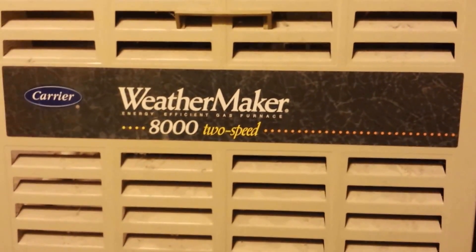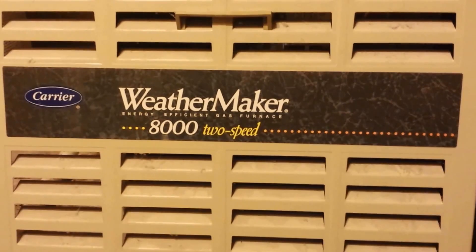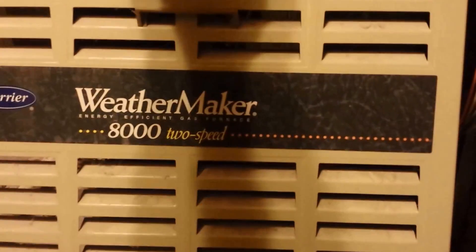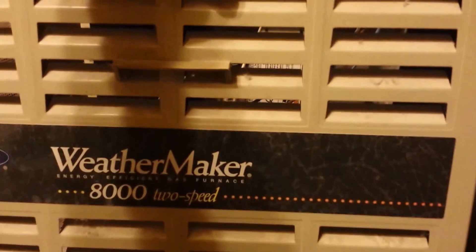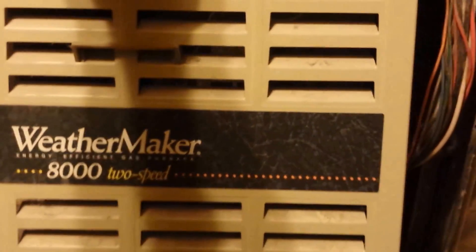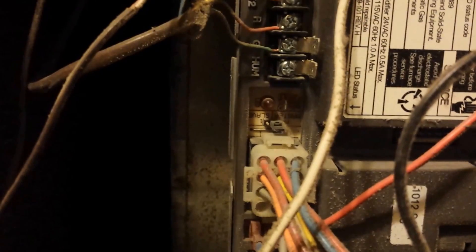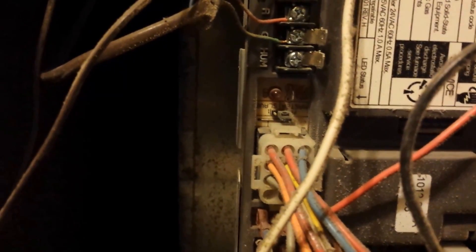I have a WeatherMaker 8000 carrier furnace that was giving error code number 33. The way you can tell is the little red indicator light will flash a code. It will flash slow and then fast, and the slow number you count and the fast number you count, and it will tell you what your error is.